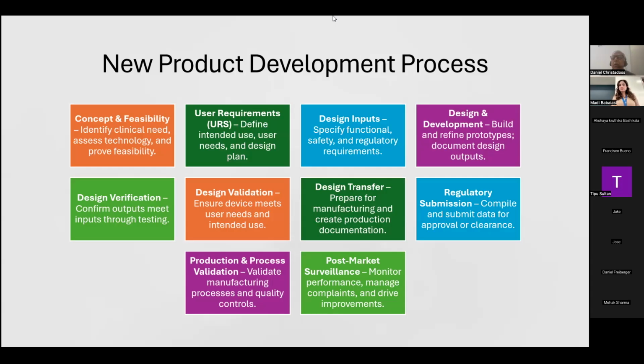So this is when you have your prototype. Again, an exciting time. You get to look at what your product is really going to look like. You have the final drawings. You have all the documents and all that is required to manufacture it. However, once you have done this, there is a phase called design verification. At this point, you have a certain output, like your drawing, and you verify through testing that the product meets those specifications. Number one is, your prototype looks like the drawing. Number two is, whatever functions the equipment or the process should have, you're able to see it. So this is called design verification. You're actually confirming it through testing.